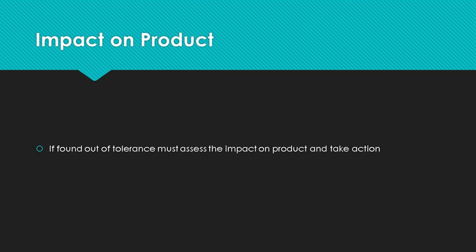In order to prevent these kinds of situations, it is important to safeguard equipment from adjustment or deterioration or damage. I see many companies keeping them in their original packaging. Do whatever works best for your company, but it is well worth your while to protect and safeguard the equipment.